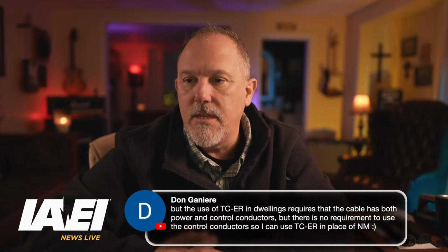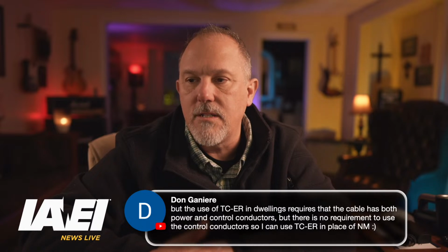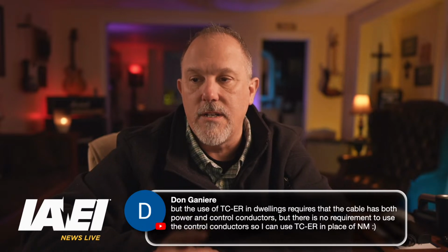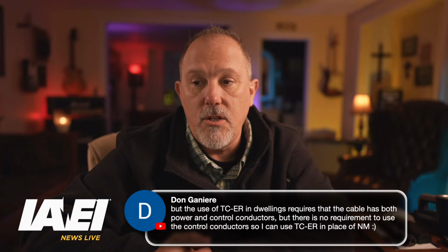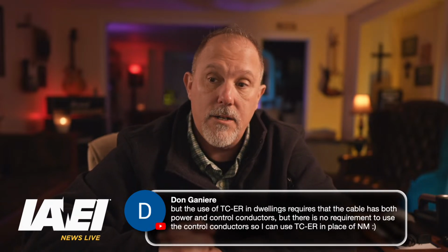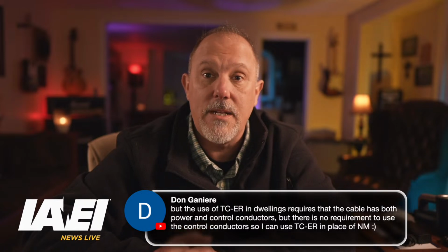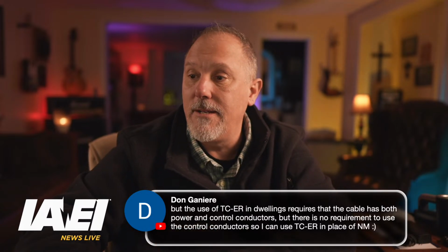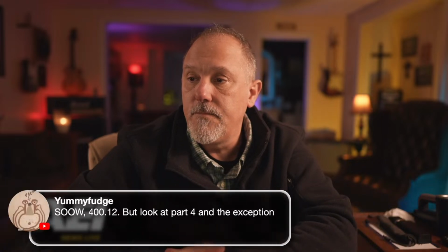Don Ganier: the use of TC-ER in dwellings requires that the cable have both power and control conductors, but there's no requirement to use the control conductors, so I could use TC-ER in place of NM. You know what, I bet, Don, it's probably a lot more expensive, and you probably wouldn't, but yeah, you could.